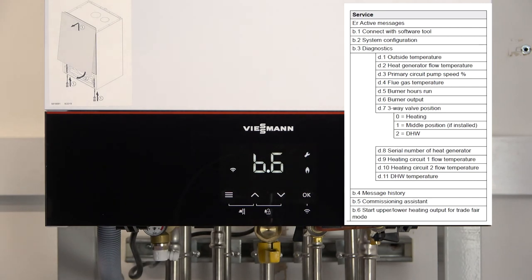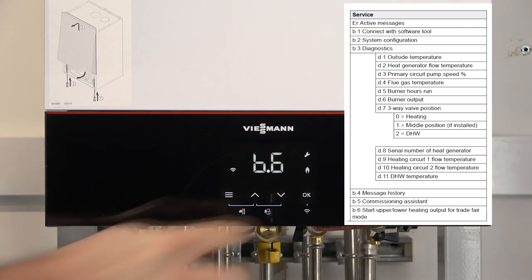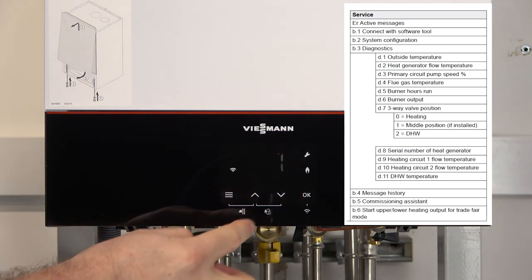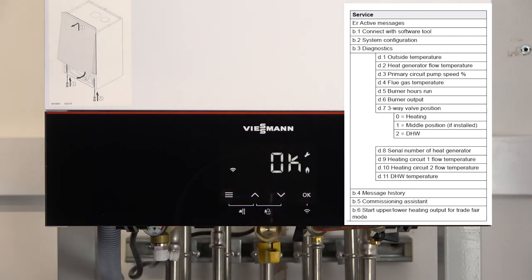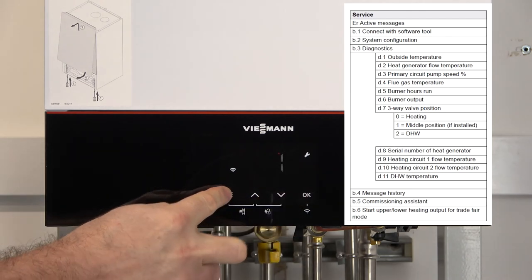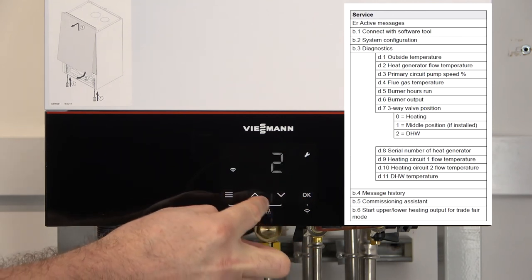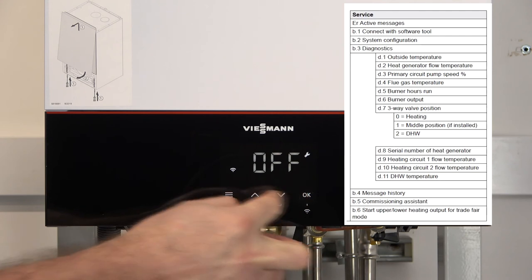And the last one we can see is B6. This one you'll be using more frequently because this is where we set the boiler into high and low. So we press OK. And at the moment it's off. So we press up to one. And this puts our boiler into high and low by going through one and two. So to B6, and we've got one and two for high and low.